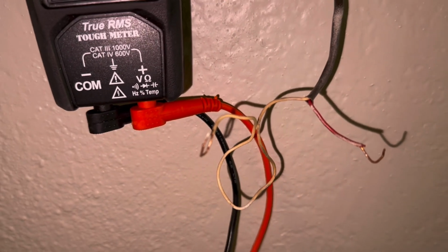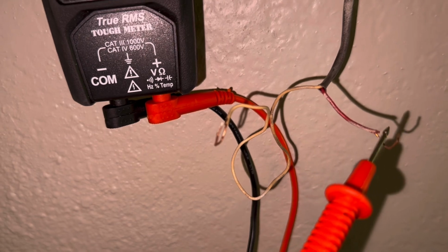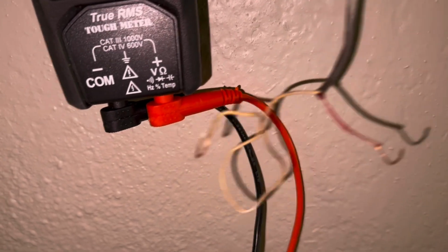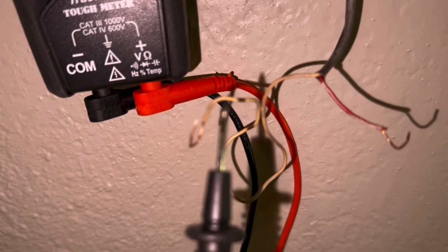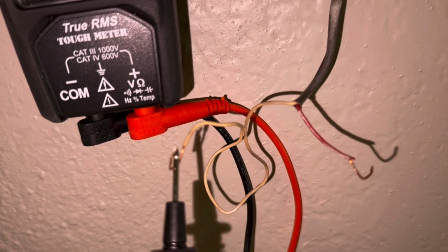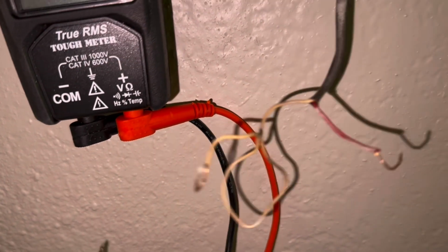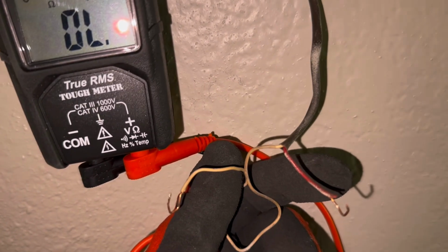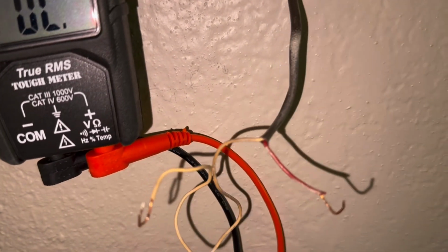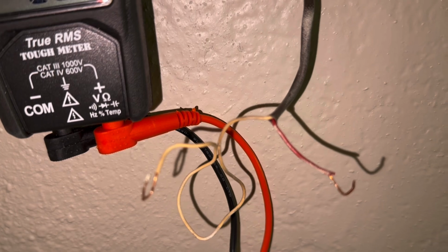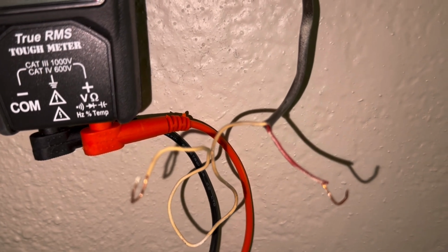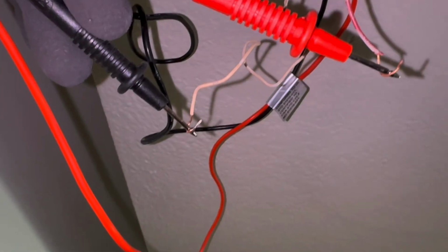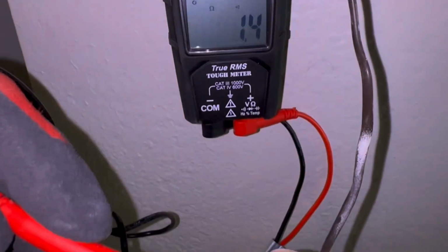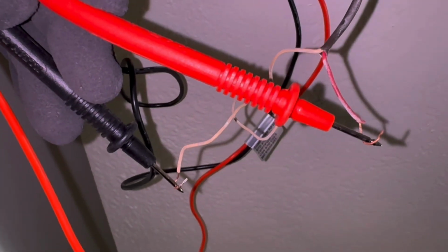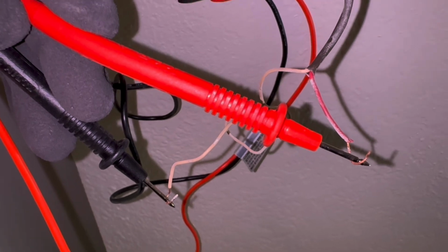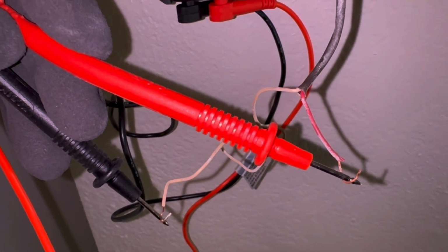What I'm going to do is I'm going to take one of my leads from my multimeter and put it on this side. My other lead to my multimeter is going to go on this side. And this helps being able to do a continuity test to make sure that there's no breaks in your low voltage wire. You can do this not only for your transformer, but you can do it for your thermostat wiring if you're working on your low voltage thermostat wiring. And that tone indicates to me that I do have continuity and there's no breaks in the line.